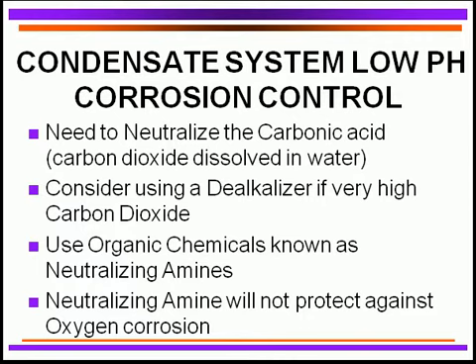Carbon dioxide dissolves in water to form carbonic acid — the same thing as in your soft drinks. There's a lot of carbon dioxide in soft drinks, and that produces carbonic acid, which is why they have low pH, down around 3 to 3.5. We don't want that to happen in the condensate line.